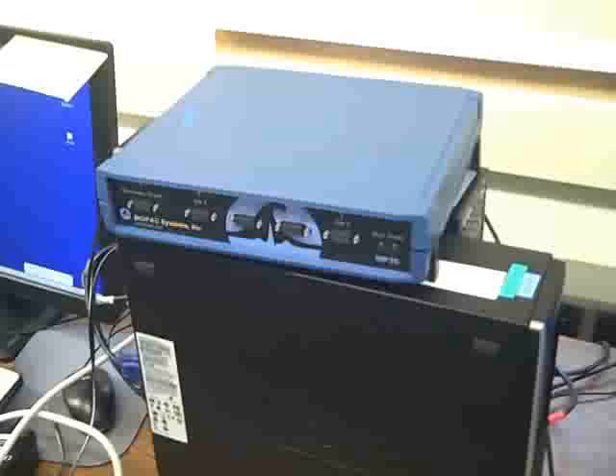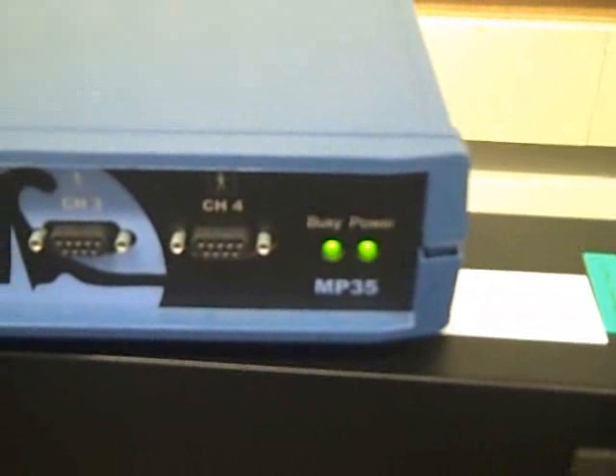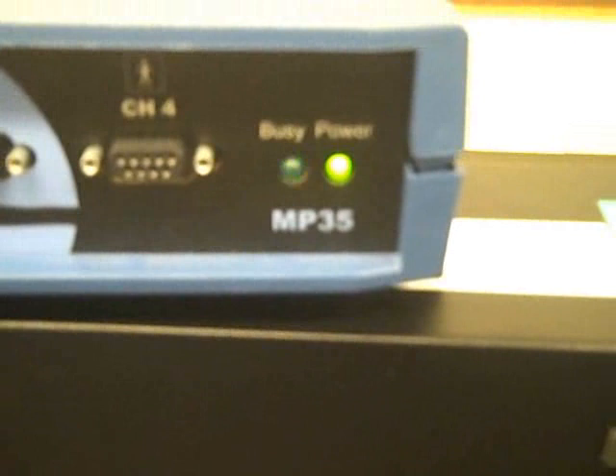You'll hear the physiological data acquisition computer give you that strange sort of three-toned bell, which essentially tells you that the blue box is now talking to the acquisition computer. And you'll have two green lights on, one for the power on the right, that should always be on, and on the left is something called a busy light, which takes, as you see it just went out, about thirty seconds depending on the model for it to turn off. The busy light just indicates the blue box has a boot up sequence that it has to do. And once it turns off, you're ready to record your data. And that endeth the lesson.